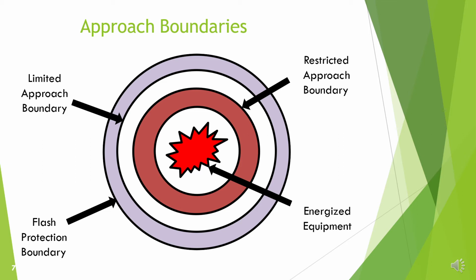Then the next area is the restricted approach boundary. This is where the qualified electrical worker will be working on the circuits or within close range of the circuits, and thus will have to have all the dielectric protection and insulated tools as well. The limited approach boundary is the next ring, and that is where the unqualified worker will be stopping.